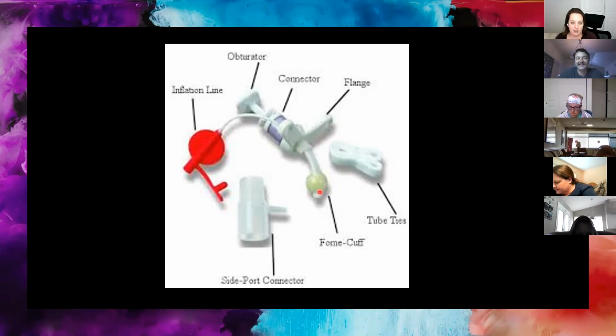So the cuff with these and with the saline cuffs, it goes up a little bit higher to help incorporate all of that area. With the saline cuff, and we'll play with those a little bit in the lab, you want to use isotonic saline, and you will use 10 cc's of saline. So when you check to see if it's inflated, you'll pull just a little bit out of the cuff because you're not going to cause a huge leak, and then make sure that it's all the way inflated.